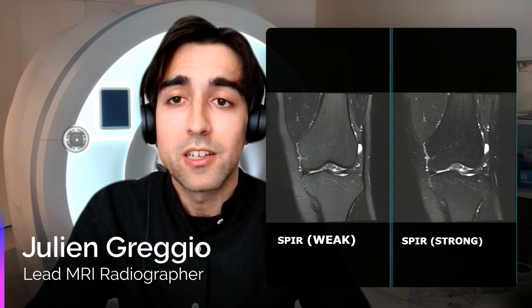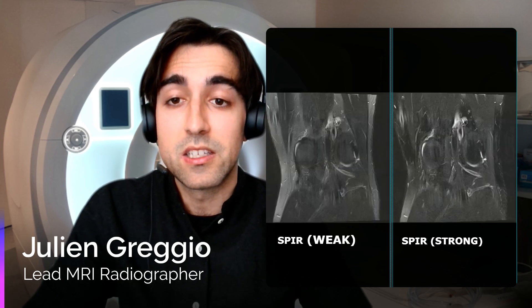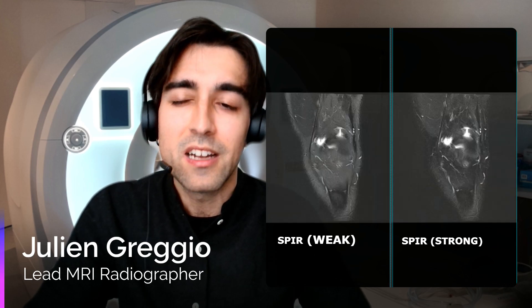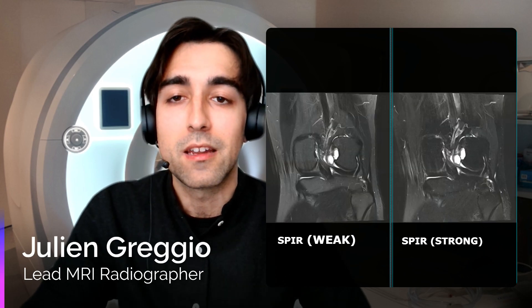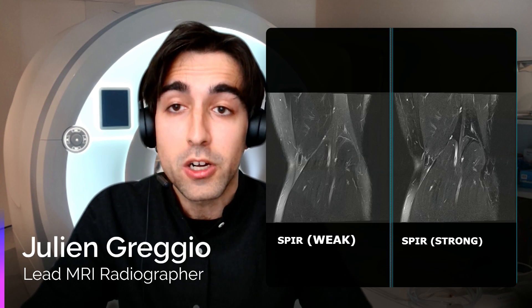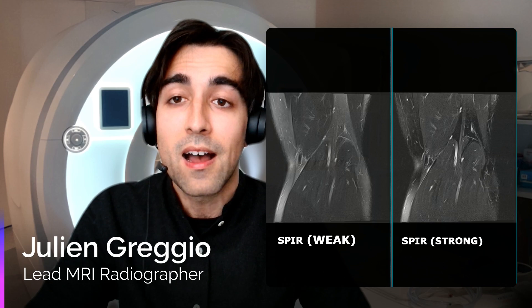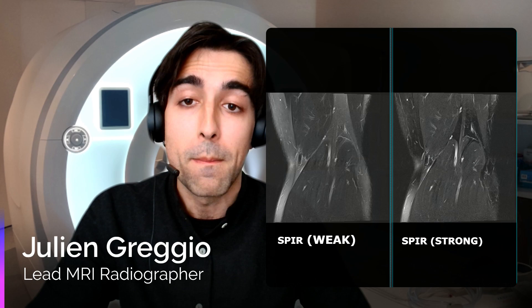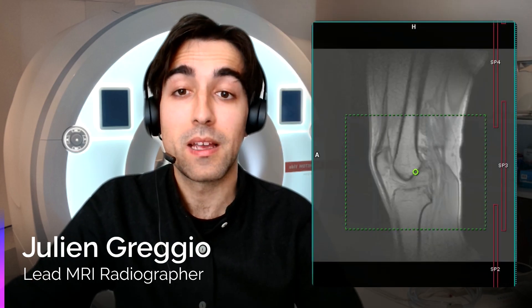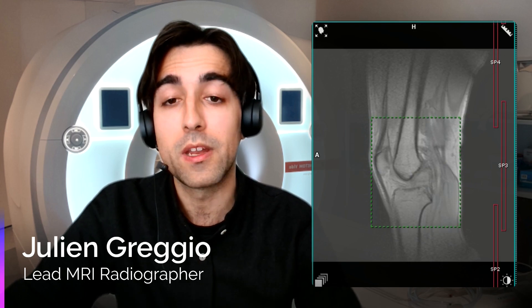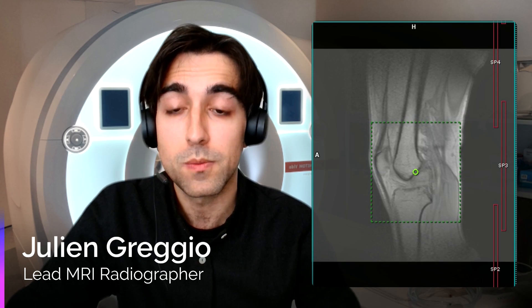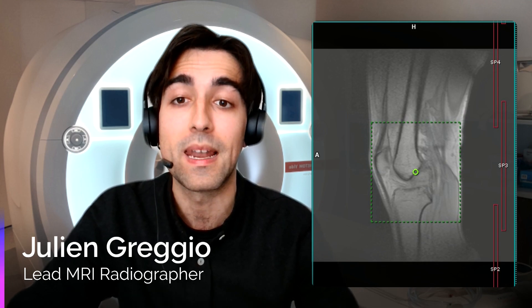This is even more pronounced for larger regions of the body. Nevertheless, regardless of the intensity of the fat saturation, SPIR sequences are generally known to be very sensitive to both B0 and B1 magnetic field inhomogeneities, so it could happen that you might struggle to achieve a good and complete fat saturation of the entire anatomy imaged with this technique, especially in the presence of metal implants for instance. Careful shimming is therefore crucial in SPIR sequences, especially when we work at very high field strength. Try, if possible, to avoid including too much air in your shim voxel — this green square box — and focus exclusively on the anatomy you want to image. Doing this is essential because SPIR is frequently used as a method of choice for post-contrast imaging, so good quality and homogeneous fat saturation plays a crucial role.